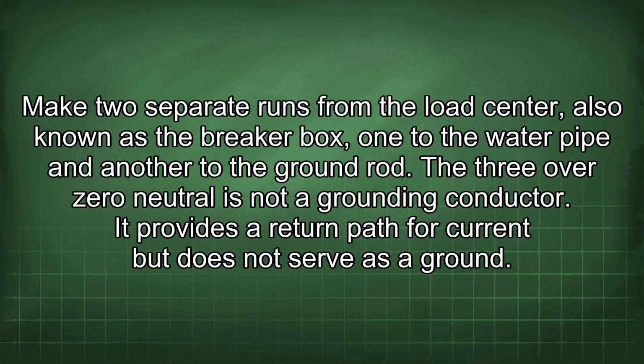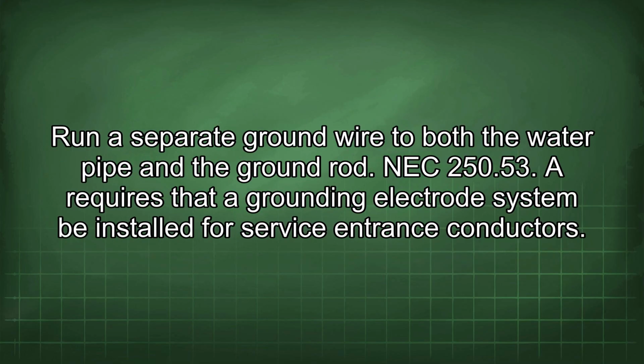Make 2 separate runs from the load center, also known as the breaker box, one to the water pipe and another to the ground rod. The 3/0 neutral is not a grounding conductor. It provides a return path for current but does not serve as a ground. Run a separate ground wire to both the water pipe and the ground rod.